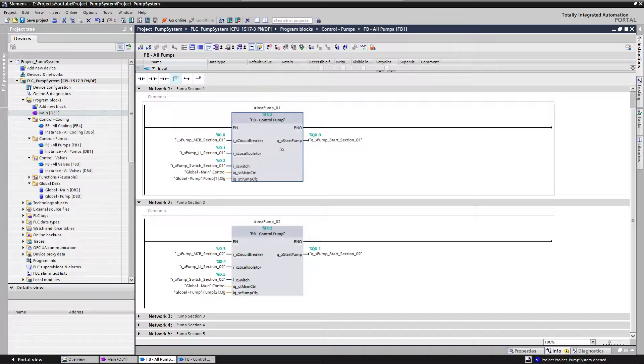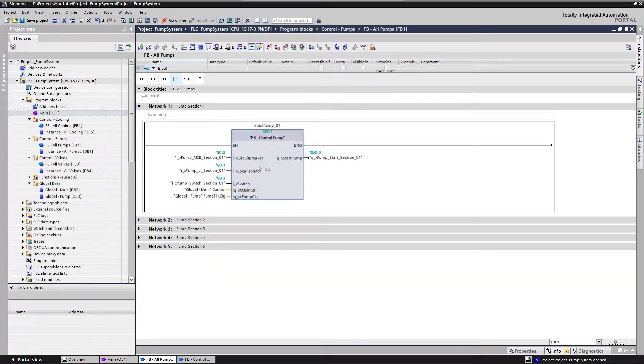Now let's have a closer look at a function block itself, taking the 'control pump' function block as an example. The function block consists of the function itself and the instance that is called with it. Next to that we have the interface: the inputs, outputs, and inouts. I normally make a habit of calling all my inputs 'I underscore', all my outputs 'Q underscore', and my inouts 'IQ underscore'. Furthermore, when an input is a boolean I put an X, when it's an integer I put an I, and when it's a structure I put ST.